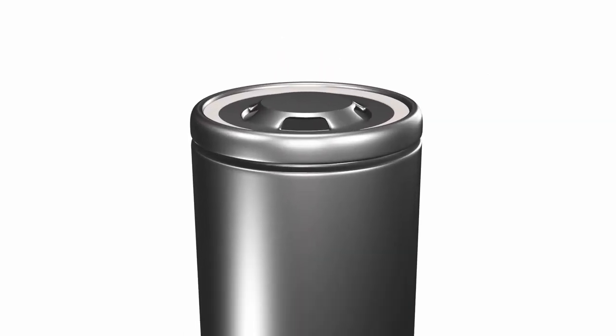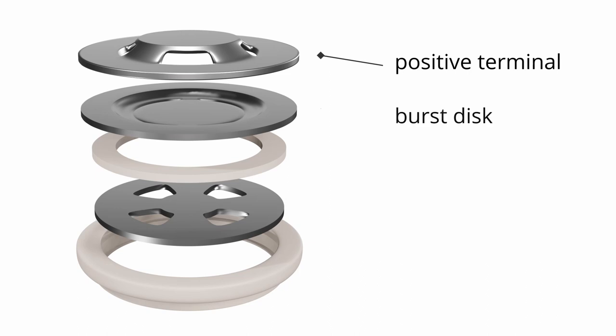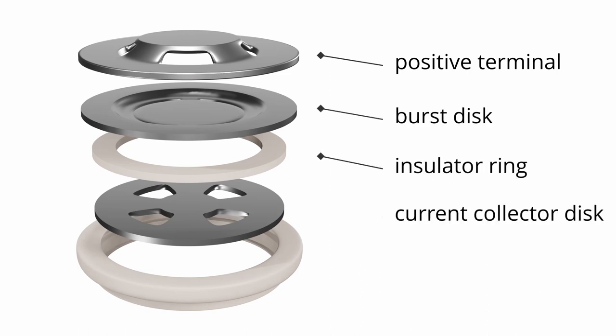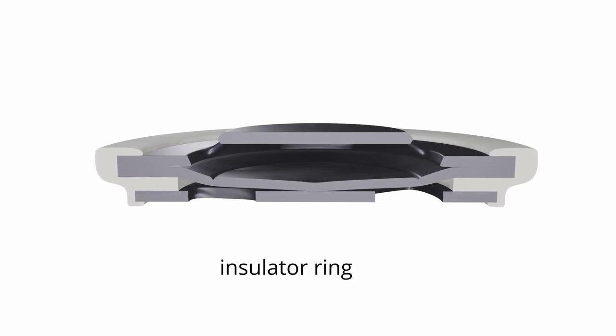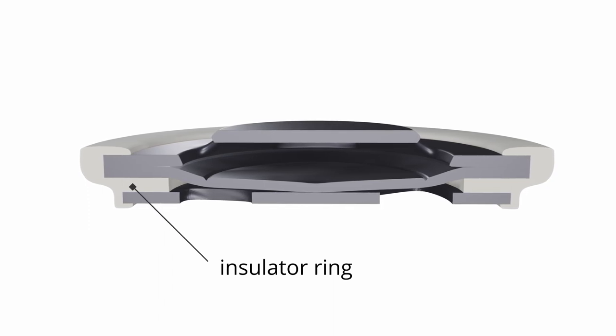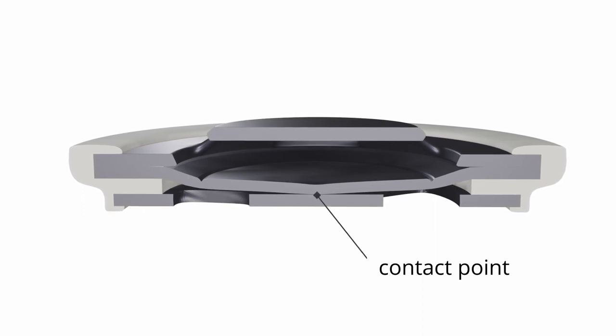If we take a closer look at the structure of the top cap, several components can be identified: the positive terminal, a burst disc, an insulator ring, and a current collector disc. The whole assembly is kept together by a sealing ring that seals and insulates the whole assembly against the cell can. The electrodes are connected to the current collector disc, so the CID has to interrupt the connection between the current collector disc and the positive terminal. To achieve this, the burst disc and the current collector disc are separated from each other by an insulator ring, except at a small contact point at the center. To guarantee a reliable, low-resistance contact between those discs, they are typically spot welded together at the contact point.